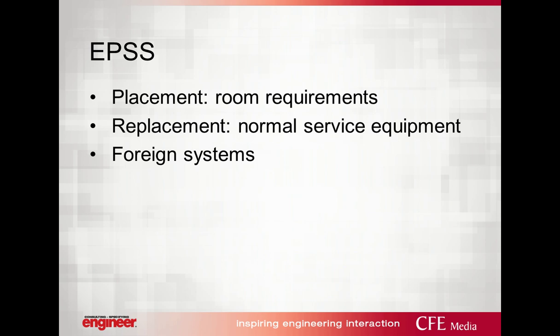I previously mentioned that the EPSS equipment requires a separate room. The definition of normal service equipment could be considered to be limited to Article 230. But we also want to understand that the only intent of this is that if I had a catastrophic failure of my normal source, I don't want that to damage my EPSS. So if I have a unit substation, for example, sitting inside an electrical room, while that might not be fed by the utility, but a campus-owned distribution system, that's still our normal service equipment for the intents and purposes of this code section. So I want to keep my EPSS separate from normal service, high amperage.